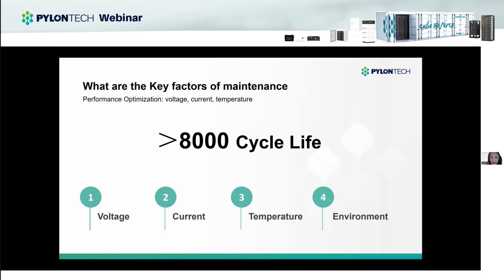And more customers care about the battery in the process of using it, the longer the life of the battery will be. Different temperatures have different effects on the life cycle. 25 degrees centigrade is the best temperature for the batteries. At this temperature, the cycle time could reach 8,000 times. And this is the reason why we suggest the customer to install batteries at the proper temperature. Too low or too high temperature would influence the C rate and the life cycle.